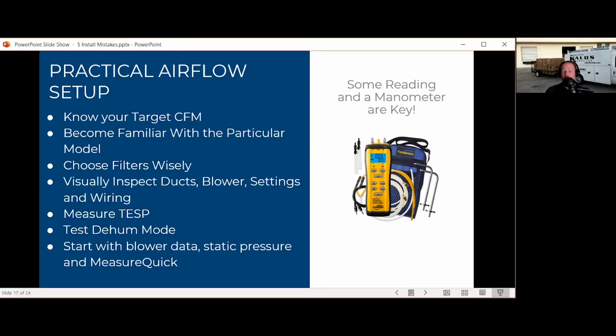in order to do the same amount of work, in order to move the target amount of air on an ECM, because most of what we're working on nowadays, because again, remember, this is install practices, this isn't service practices. Most of what installers are facing today are ECM blowers. It's going to produce that target up to a pretty extreme range. You're going to generally have to get to about 0.7, 0.8, 0.9, 1 inch of static before they stop producing what they're supposed to produce.